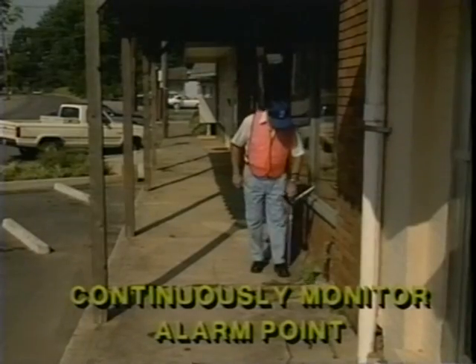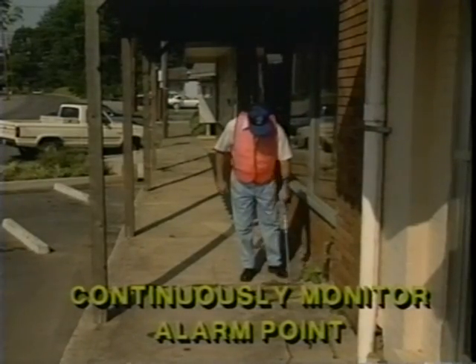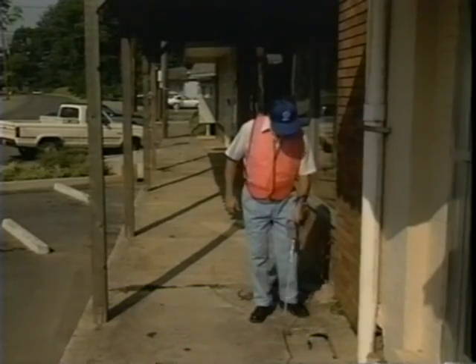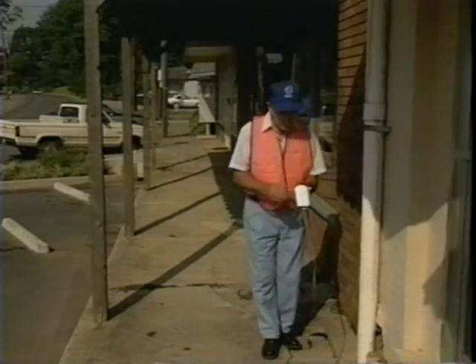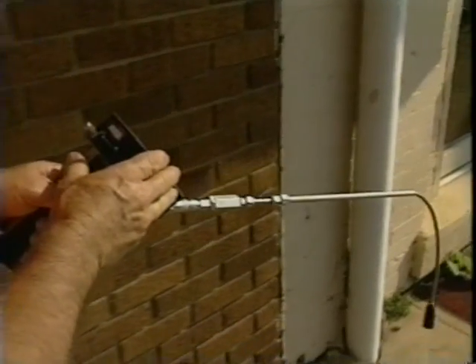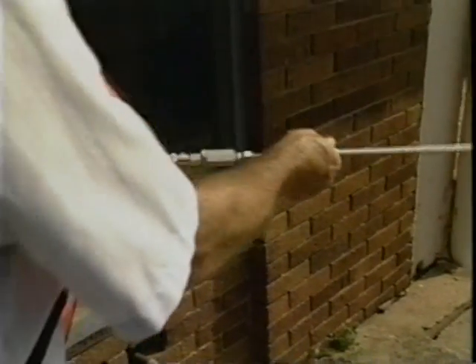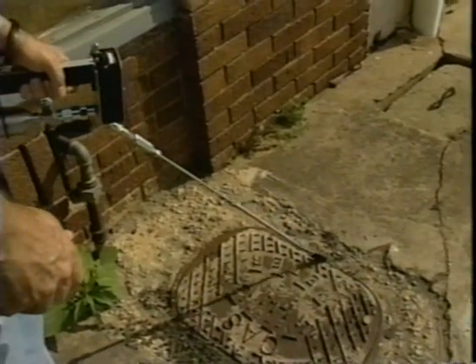During any survey for gas leaks, be sure to keep the meter adjusted just below the alarm point. It is extremely important that this setting be continuously monitored during the survey. Every survey is different and requires slightly different sensitivity settings. Keep the meter as close to the alarm point as practical in order to assure maximum detection sensitivity.